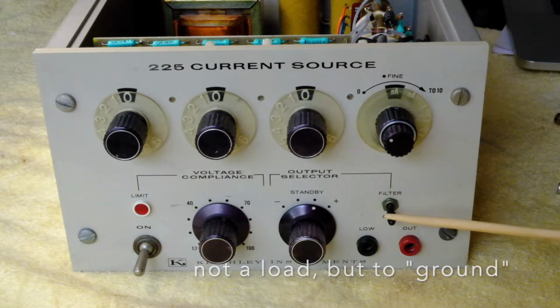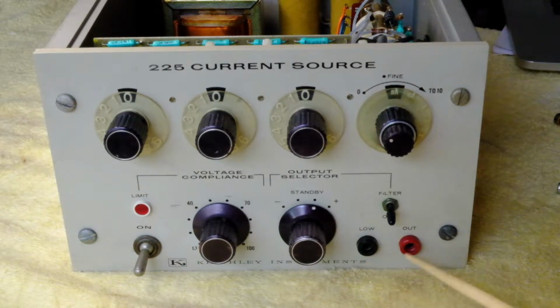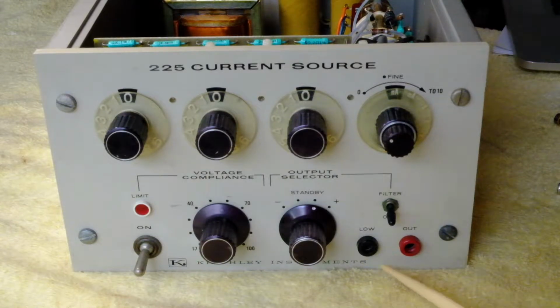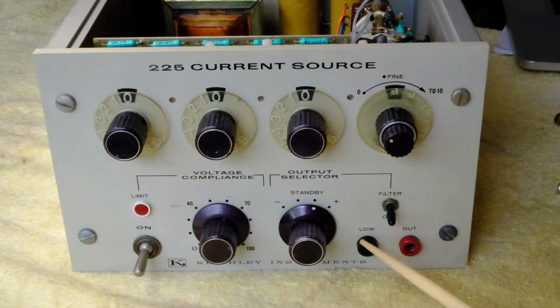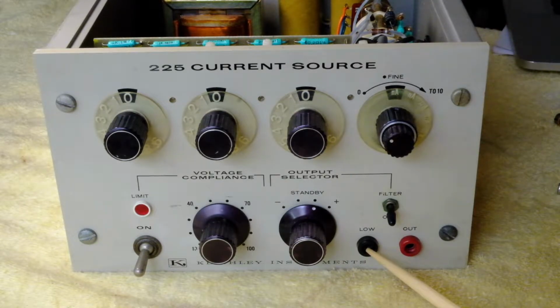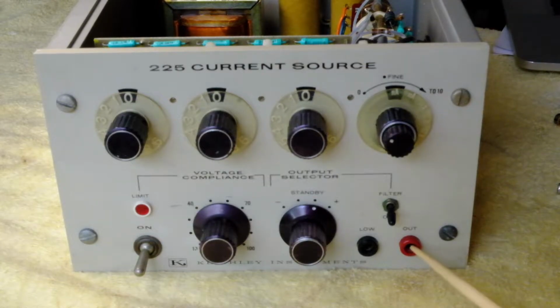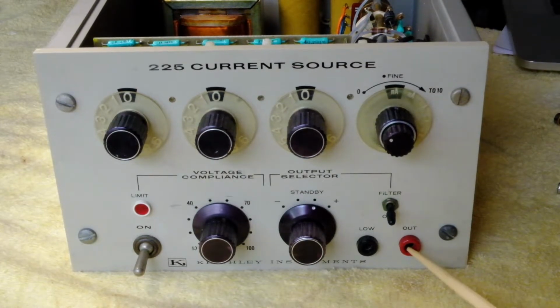You have a filter that allows you to filter some of the noise that may be on this, and this is the low and the high outputs. The low is in this particular instrument connected to the chassis at the back, and high is basically whatever current output you're setting. It can be either input or an output current.